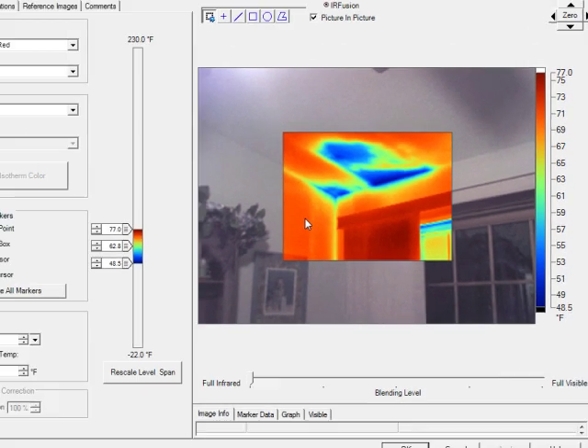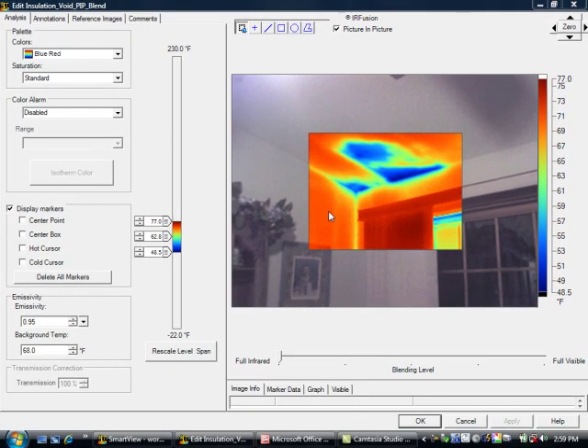Now this is to be understood in context that your camera is plus or minus two, usually plus or minus two degrees accurate in the original calibration of the factory. Plus your thermal hygrometer which gives you the dew point. Is it accurate? That's the question.